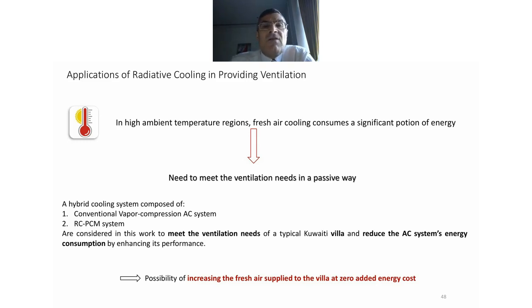So we're going to be looking at this application, plus the application that Dr. Surur mentioned to improve the COP by cooling the air going over the condenser. He mentioned it very well and clearly that if the air is cooler going over the condenser, the COP will improve. And this peak load is during the day where the temperature is very high.